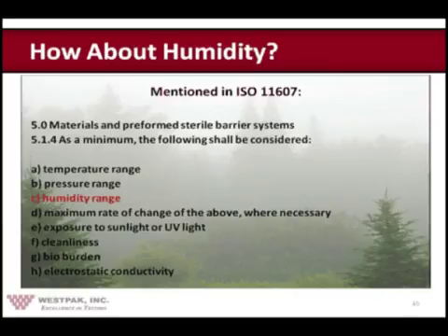Another question that we're often asked, and one that is a source of much confusion, is how about humidity? Okay, well, let's tackle this one, shall we? Humidity is mentioned in the ISO document 11607, but look here, it only mentioned it as item 5.1.4, as a minimum the following shall be considered. Okay, temperature, pressure, and oh, look at this, humidity.